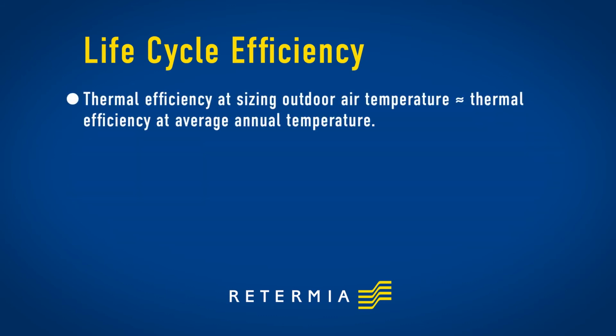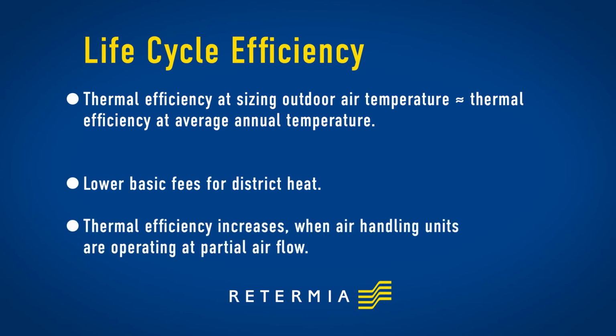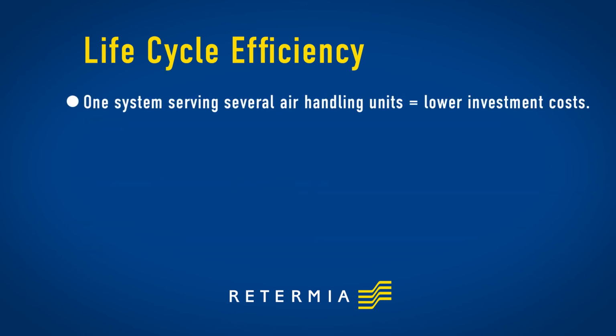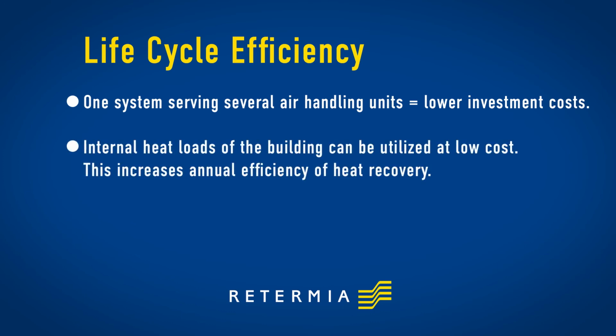Thermal efficiency is almost constant in the Retermia system, regardless of outdoor air temperature. This means lower basic fees for district heat. In addition, the thermal efficiency of heat recovery increases when air handling units are operating at partial airflow. A heat recovery and cooling system serving several air handling units lowers the investment costs. The internal heat loads of the building can be utilized in the heat recovery system at low cost. This increases the annual efficiency of heat recovery.